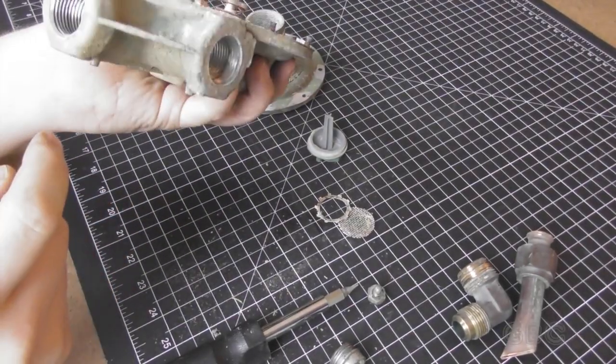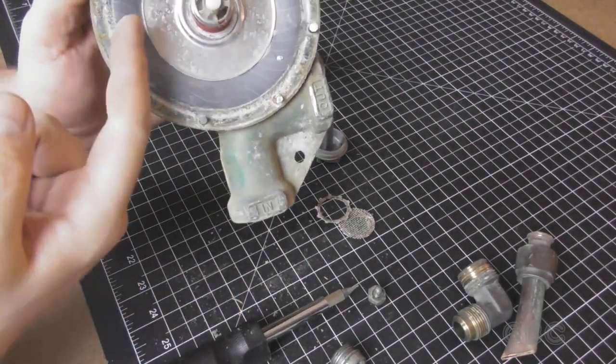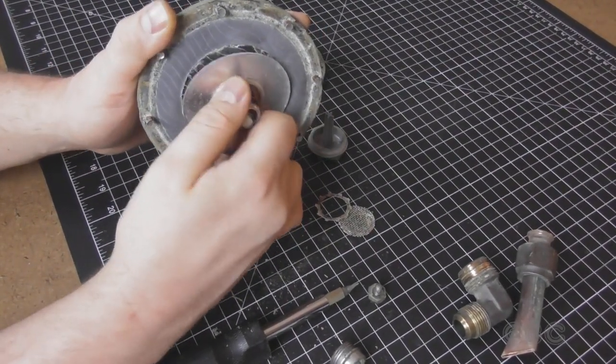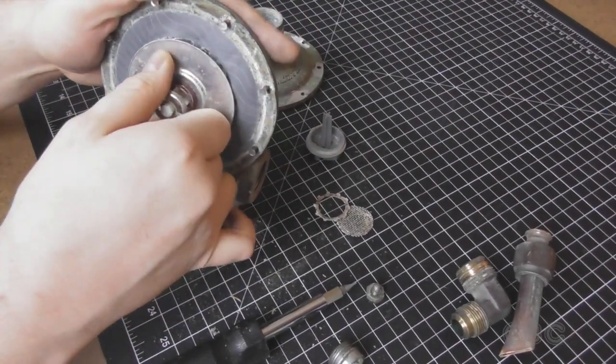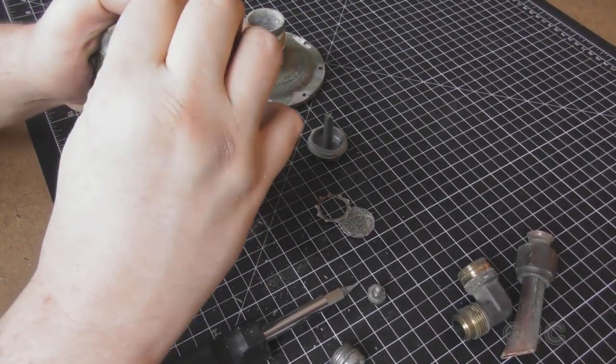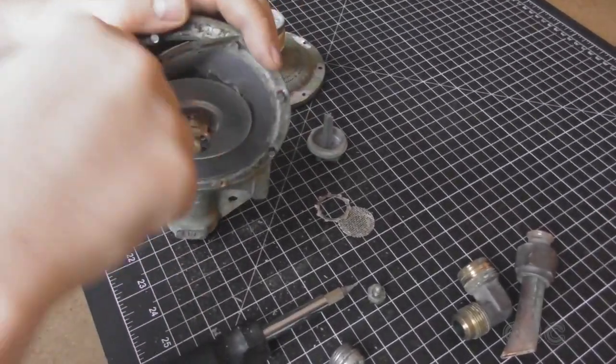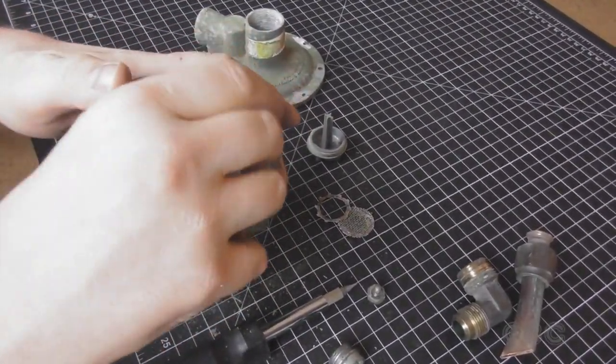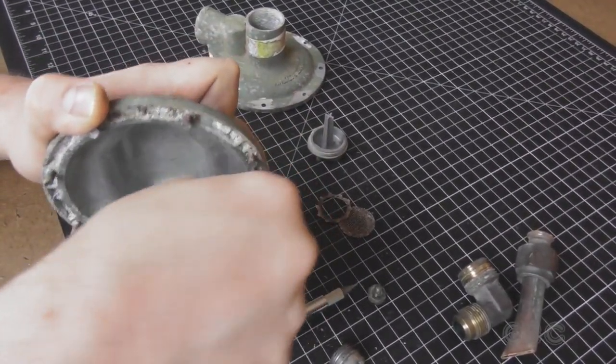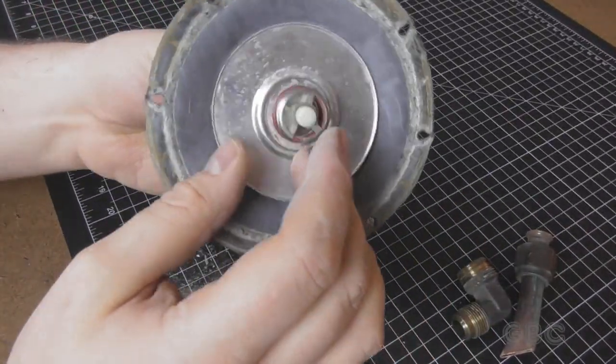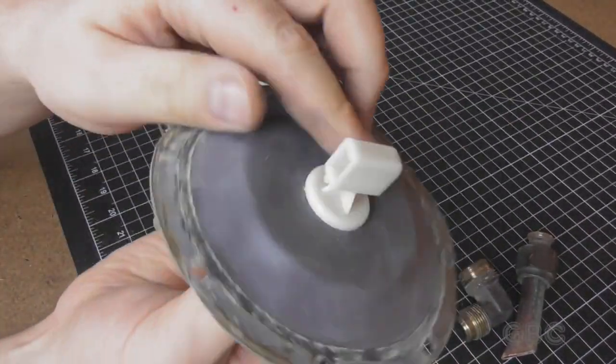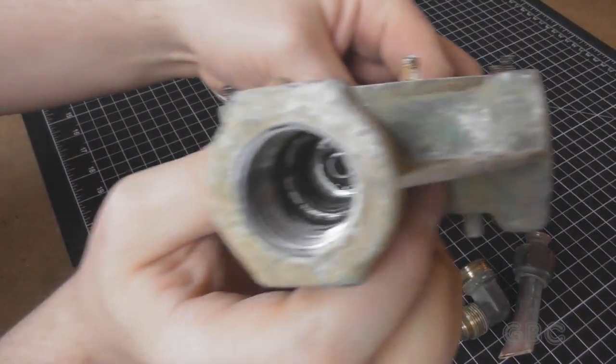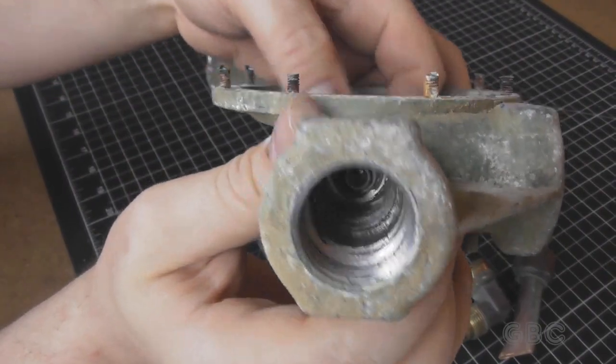So the gas comes in here through the input and pushes against the back of the diaphragm against the pressure of the spring. I'm going to pull this apart. And on the back of the diaphragm there's this plastic block and that actuates this lever. That is what is opening and closing the inlet valve. It's moving that rubber headed bolt up and down.